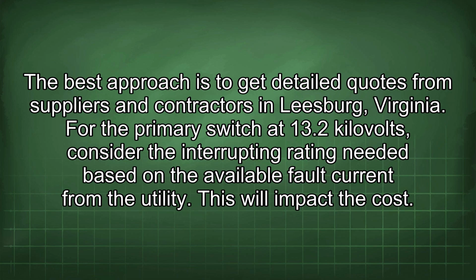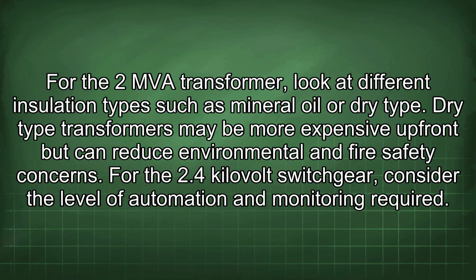For the primary switch of 13.2 kV, consider the interrupting rating needed based on the available fault current from the utility. This will impact the cost. For the 2 MVA transformer, look at different insulation types such as mineral oil or dry type. Dry type transformers may be more expensive upfront but can reduce environmental and fire safety concerns.